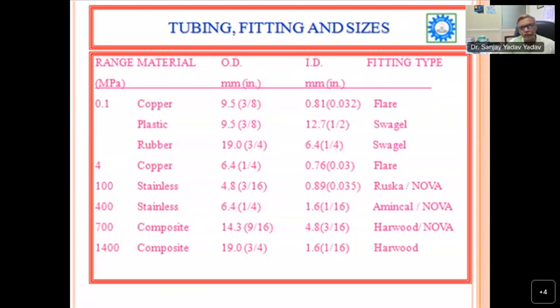These are some tubing fittings and the sizes of tube with respect to pressure range. At lower pressure, you can use copper, plastic, and rubber tubing. Up to 4 megapascal, you can use copper tubing, and above that you can use stainless steel tubing up to 100 megapascal. Up to 400 megapascal, there is another fitting type, such as Autoclave or Nova. At 700 you can use composite, and above 700 you can use composite materials.